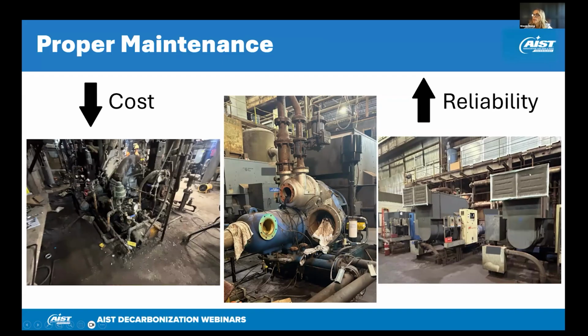These are on motors. These need to be changed. Also, there are filters on the mezzanine that needed to be changed. This machine was down for an overhaul. This should have been properly covered to eliminate any contaminants from the ambient air being ingested in this compressor. And over here we have oil leaks in the compressor tubing, and those could be fixed for safety purposes.